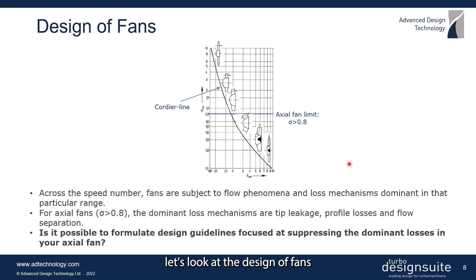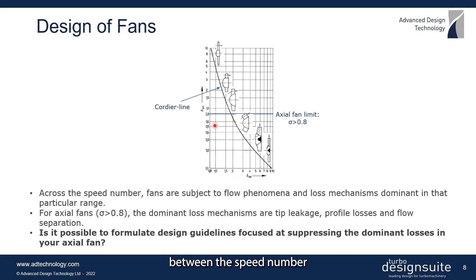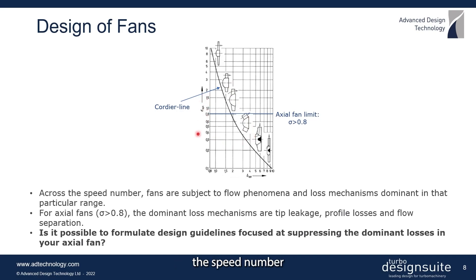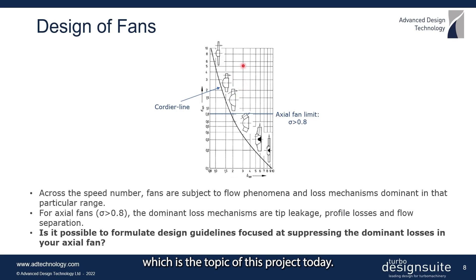Now let's look at the design of fans in a bit more detail. This chart provides the relationship between speed number and diameter number as experimentally found by Cordier. This relationship, called the Cordier line in the literature, represents optimum fans with high efficiency. There is a relationship between speed number or diameter number and the type of fan to be used — axial, diagonal, or radial — in order to obtain high efficiencies. Across the speed number range, fans are subject to various flow phenomena and loss mechanisms, with tip leakage, profile losses, and flow separation being dominant for axial fans.